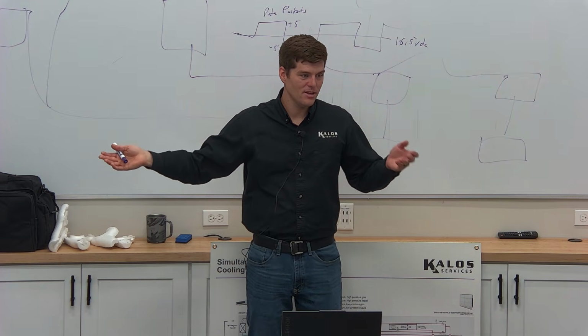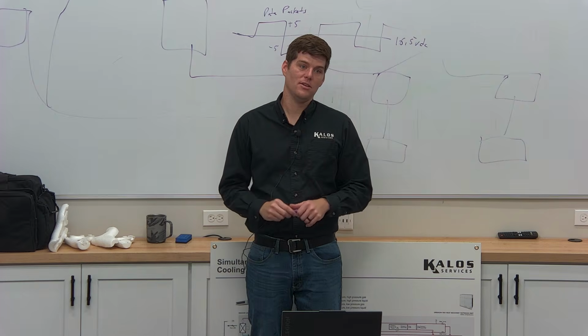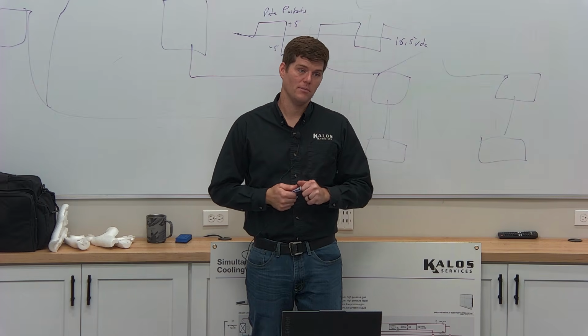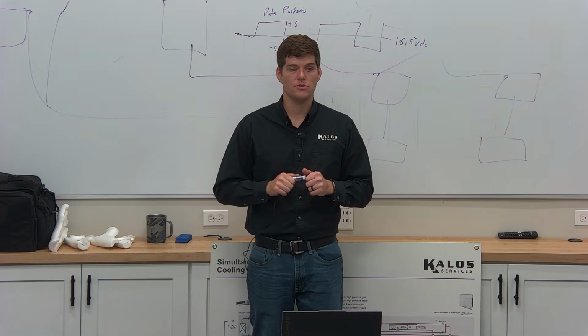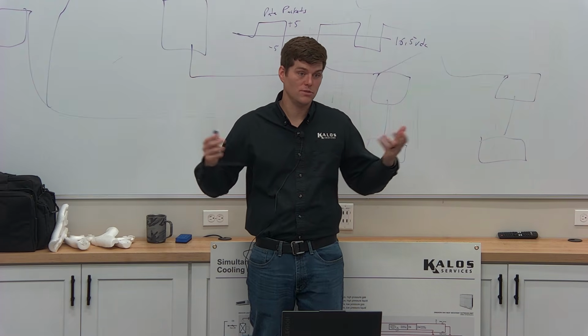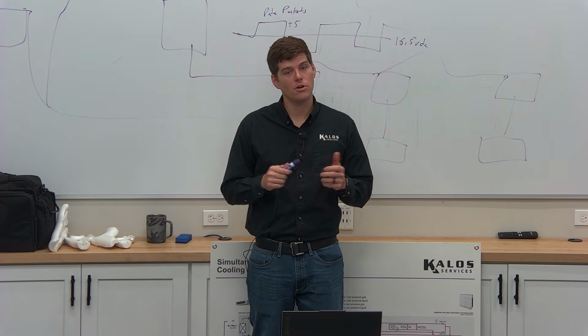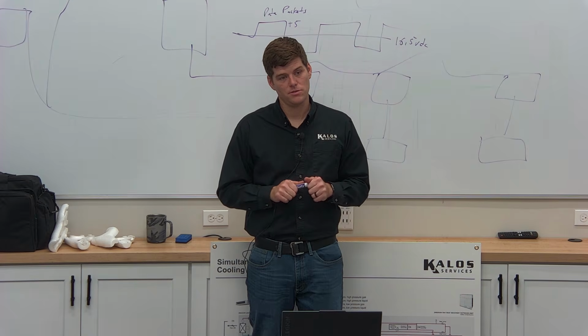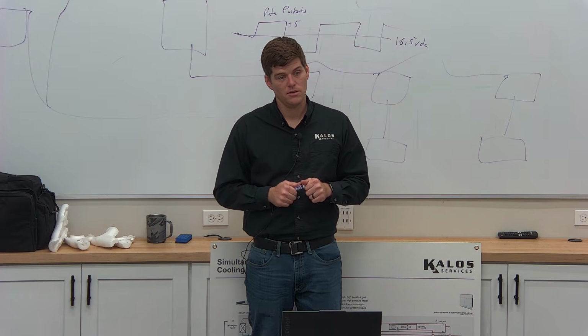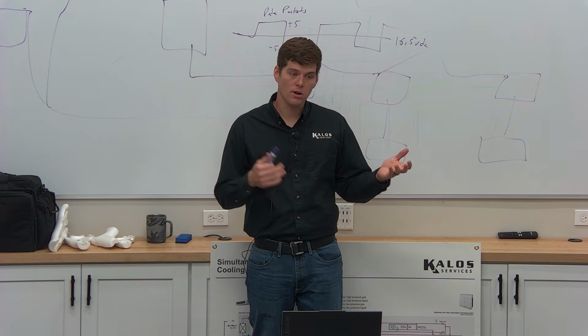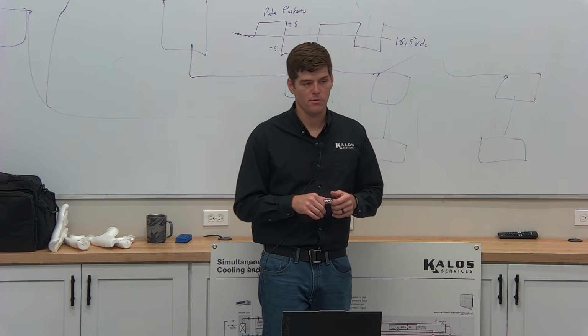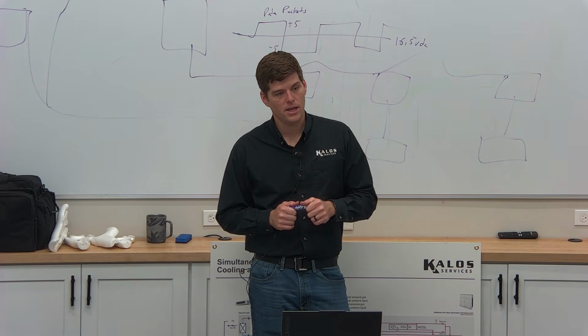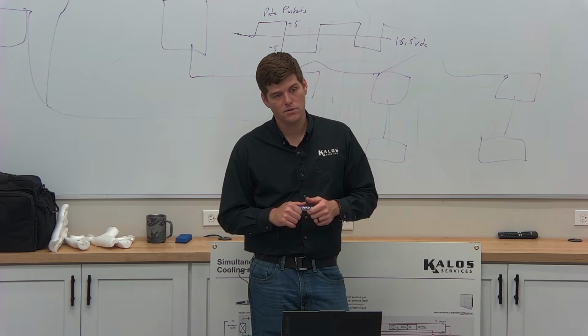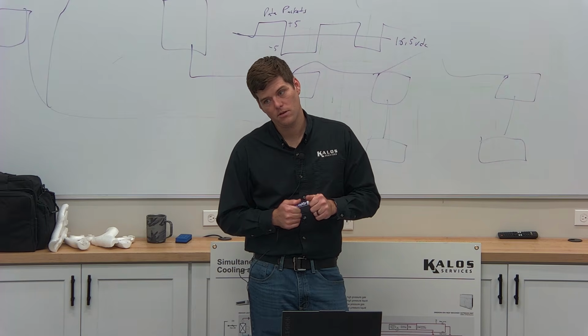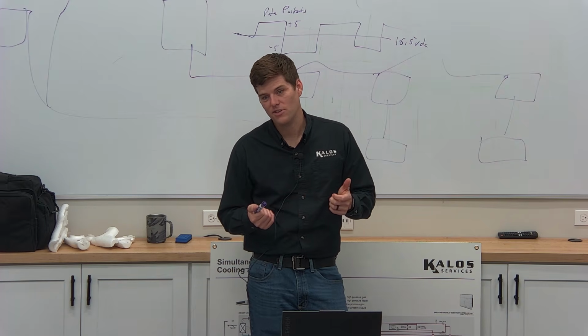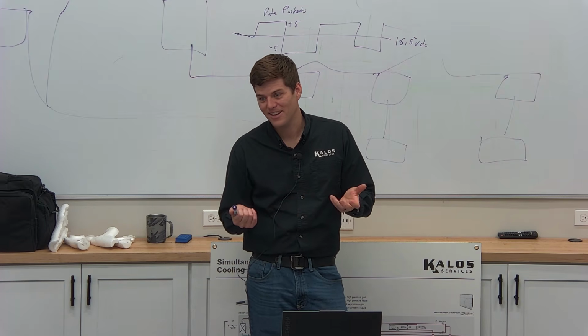to find the problem in the first place. So when you go to a system like this, you have to make sure that you're given the right amount of time. And that's on me, that's going to be on Sam to understand what those time frames are in general. But if you're going to record data, the minimum I say is 2 hours of operational data, turning it all the way on. And you can call me if you're going to go to a call, and I can prep you for it. I can't tell you how many times I got sent data. Here's 15 minutes of data. Tell me what's wrong. Unit didn't even turn on in the 15 minutes. Like, what do you want me to tell you?